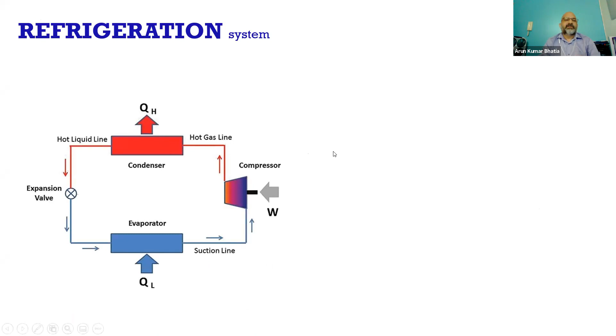Now let's come to the core engineering topic. This is the basic refrigeration system, called the vapor compression system. The compressor compresses the gas from low temperature, low pressure to high temperature, high pressure. Then it goes into the condenser where it condenses to become 100% liquid. That liquid goes through the expansion valve, a throttling process, where in direct expansion it becomes mist, and then it enters the evaporator where we are sucking the heat, and the cycle goes on and on. The red area is the high temperature, high pressure area, and the blue area is the low temperature, low pressure area.